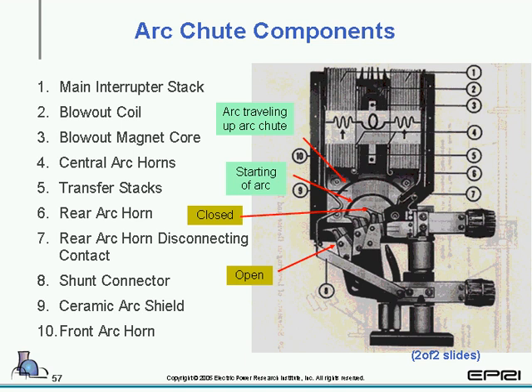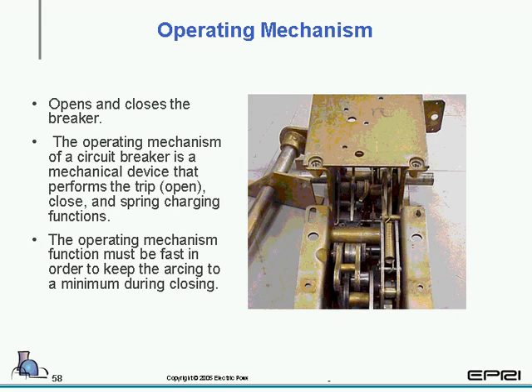And that pretty much concludes all the different types of mediums in which to control and extinguish the arc. Next one we're going to take a look at is the operating mechanism. Now, the operating mechanism is used to open and close the circuit breaker. The operating mechanism of the circuit breaker is a mechanical device that performs trip, close, and spring charging functions. The operating mechanism function must be fast in order to keep the arcing at a minimum during closing.